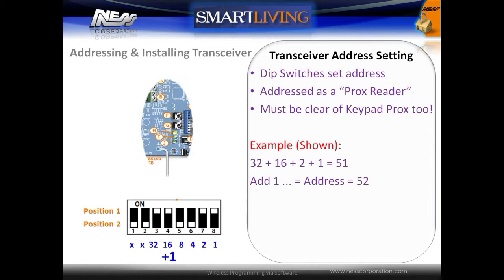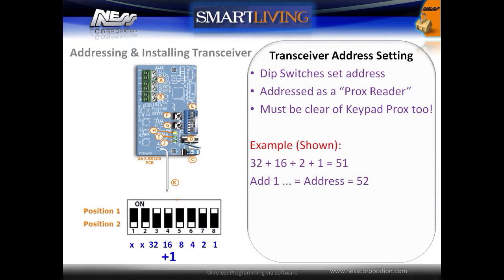The transceiver is addressed using the onboard DIP switches. When addressing the transceiver, care must be taken to make sure it does not conflict with prox readers on the system. Switches 8 to 3 correspond with binary digits. With all switches off and a value of 0, this corresponds with module number 1 on the system, which means we always need to add 1 to the total number of the DIP switches.